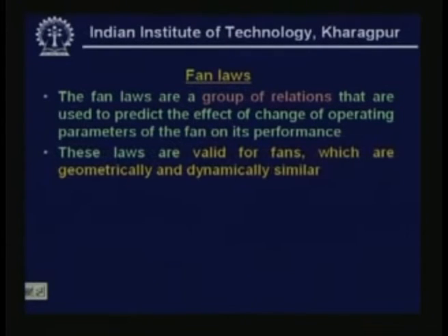These laws are valid for fans which are geometrically and dynamically similar. If the fans are geometrically and dynamically similar, you can apply the fan laws. If they are not, you cannot use them. For example, you cannot use the fan laws for comparing performance of a forward curved blade with a backward curved blade. They are not geometrically similar, so you cannot use fan laws for these two.